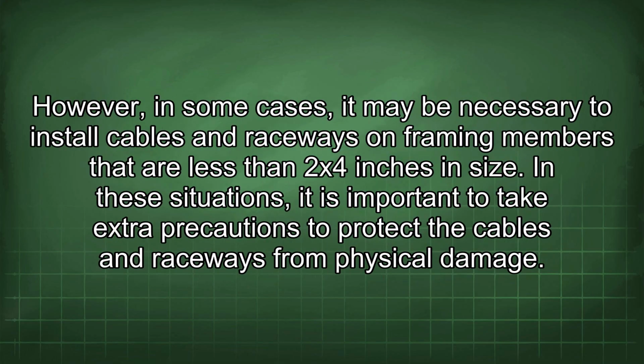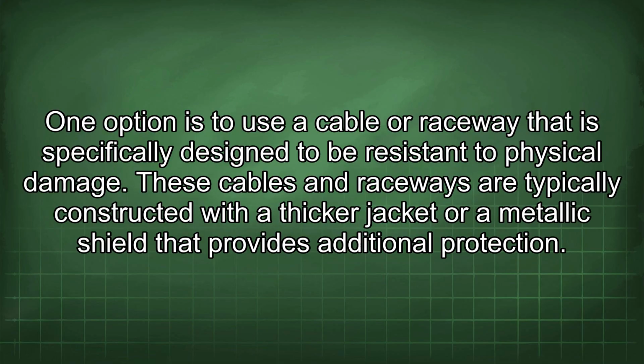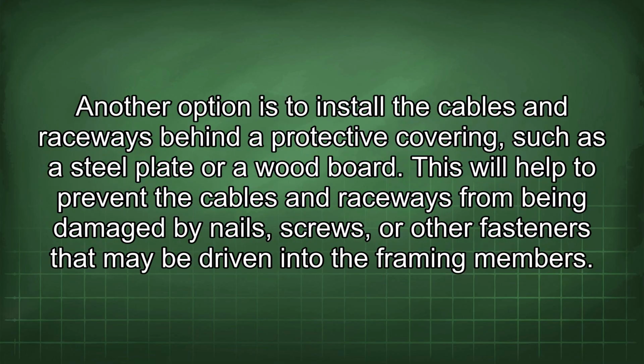However, in some cases, it may be necessary to install cables and raceways on framing members that are less than 2x4 inches in size. In these situations, it is important to take extra precautions to protect the cables and raceways from physical damage. One option is to use a cable or raceway that is specifically designed to be resistant to physical damage. These cables and raceways are typically constructed with a thicker jacket or a metallic shield that provides additional protection. Another option is to install the cables and raceways behind a protective covering, such as a steel plate or a wood board. This will help to prevent the cables and raceways from being damaged by nails, screws, or other fasteners that may be driven into the framing members.